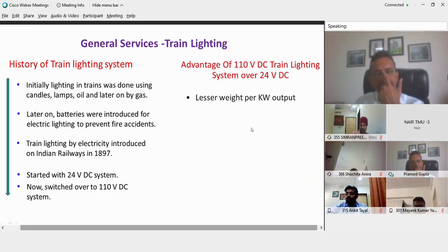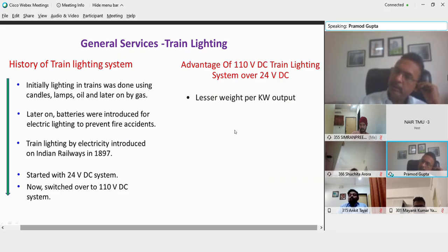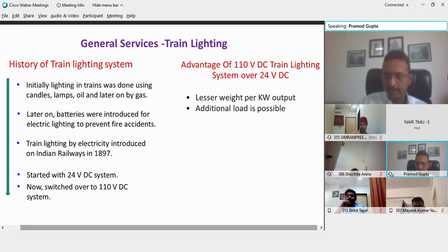These are some advantages of the 110 volt DC system. It has lesser weight per kilowatt, and additional load is possible. If the generating system of one coach becomes defective, it is possible to extend power supply from the adjacent coach, which was not possible in the 24 volt system. As a result, if something went wrong with the generating system of a 24 volt coach, the coach would remain dark during the entire journey, which was quite uncomfortable for passengers. So we changed over to the 110 volt DC system.